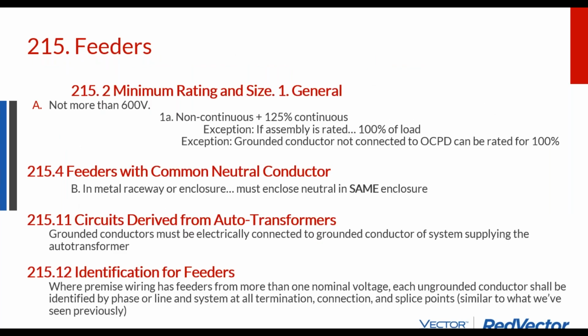So now we get into the sizing of our feeders, and we have minimum feeders for under 600 volts: you rate to the non-continuous load plus 125% of the continuous load. There's an exception that says, well, if your whole assembly is rated for 100% of the load, your feeder needs to be able to supply 100% of the load. So sometimes you'll have additional fuses or protections that will blow or stop the circuit from functioning when it reaches past that 100%. And then you follow the manufacturer's instructions.